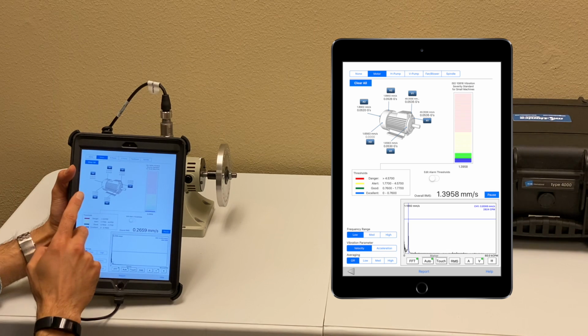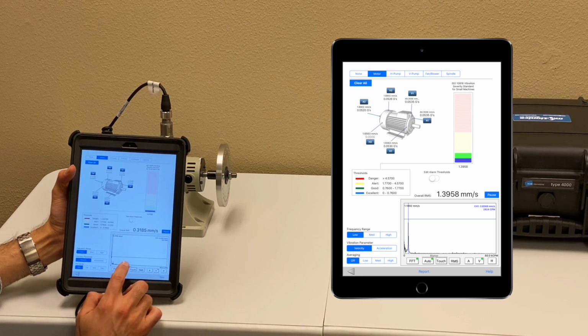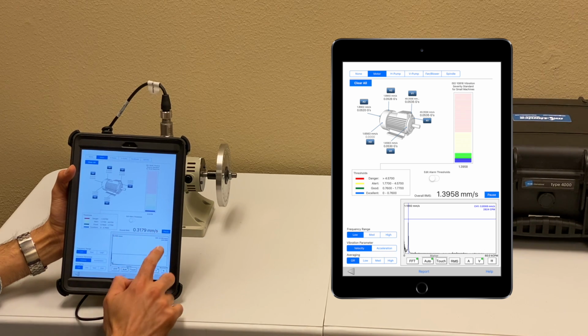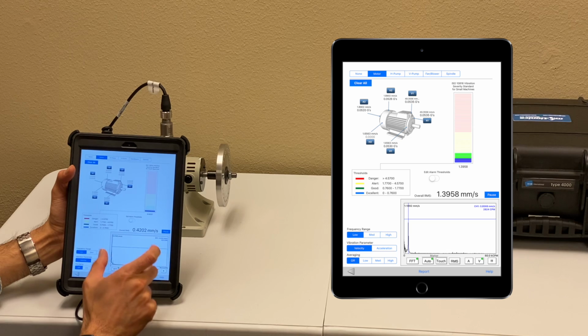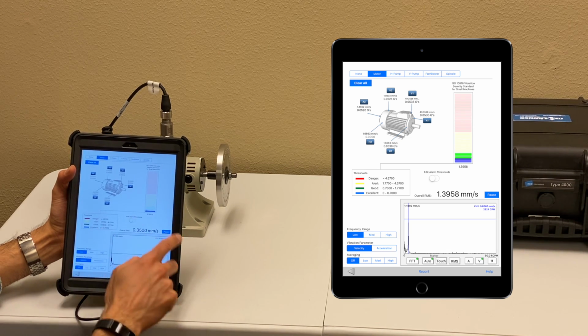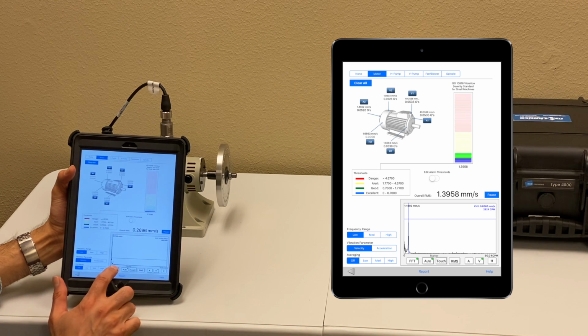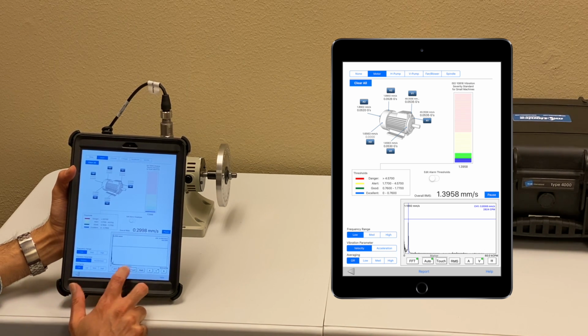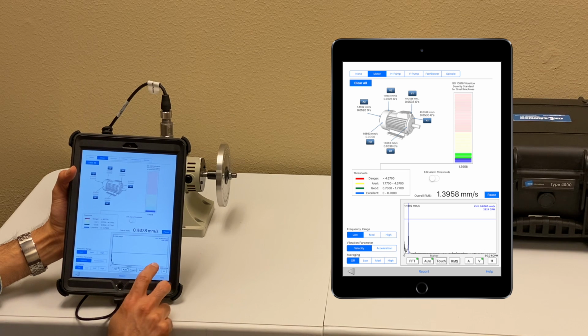When you capture each point, it's also going to capture the overall spectrum and a screenshot of that spectrum. It's going to save it to your report, and you can see that. On the bottom part, there's a small window showing the spectrum. You can switch to time waveform or a spectrum FFT. It has a marker and an auto peak detector. It shows overall RMS, and you can switch between acceleration and velocity. You can pause and play. Again, if you're trying to do deeper vibration analysis, it's better to use our other app for analyzing your spectrum and time waveform. This one is only to show you a quick view of your overall signal.